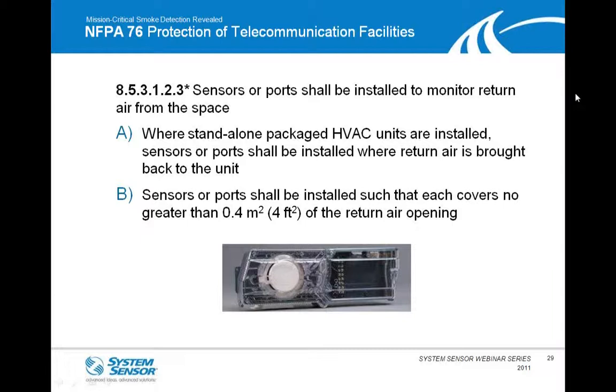Now again, aspiration is a great method and tool for smoke detection in these facilities. You can put the sampling pipes directly across the front of the return grill or within the ductwork. But I do want to point out also that high sensitivity duct smoke detectors, which System Sensor does offer, are also a great solution. Depending on the size of your return air duct or grill, you may need to use 2 or 3 duct smoke detectors in order to meet that 4 square foot coverage area. But it also does provide an alternative to aspiration.